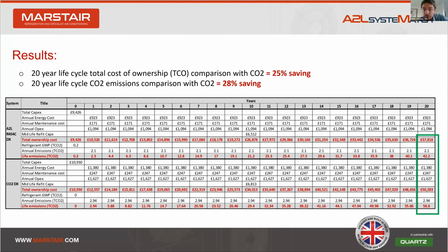From a life emissions of CO2 point of view, the initial refrigerant charge of A2L with a GWP of 148 is slightly higher than a direct CO2 system, obviously. However, this difference is so small it's almost insignificant compared to the emission savings achieved through the reduced energy usage.